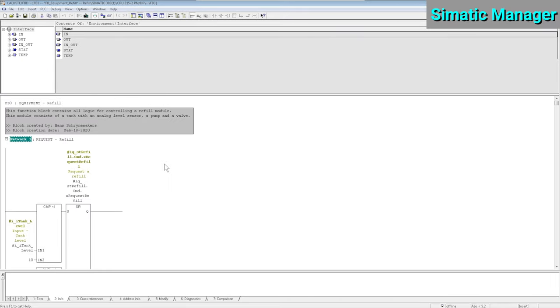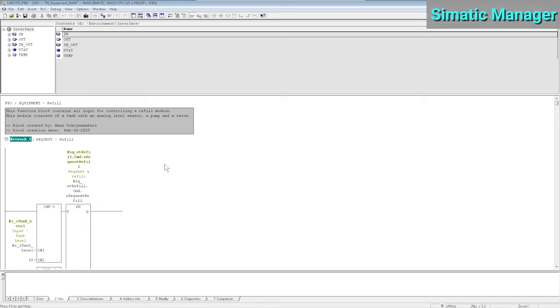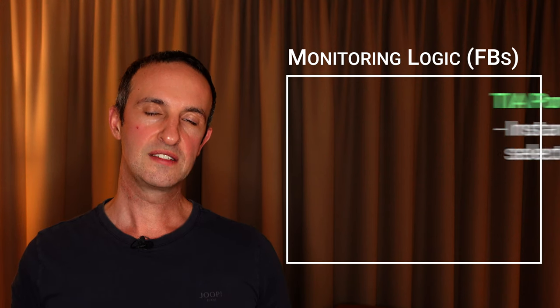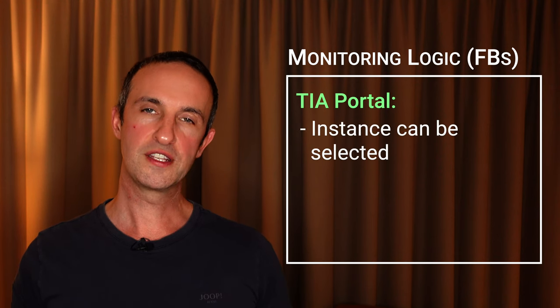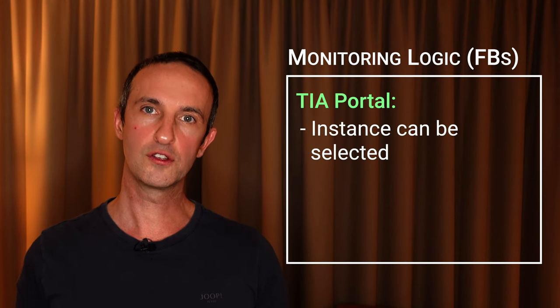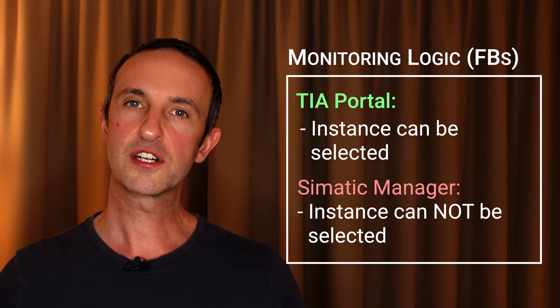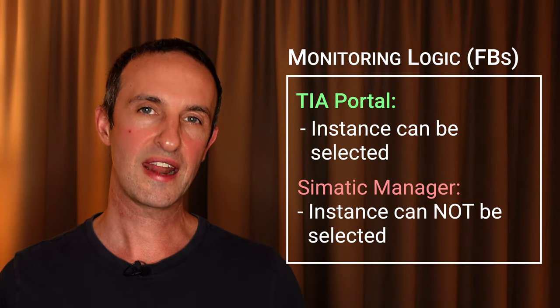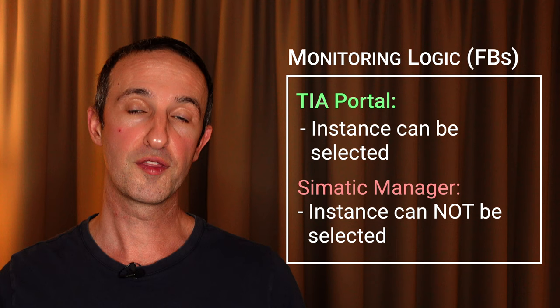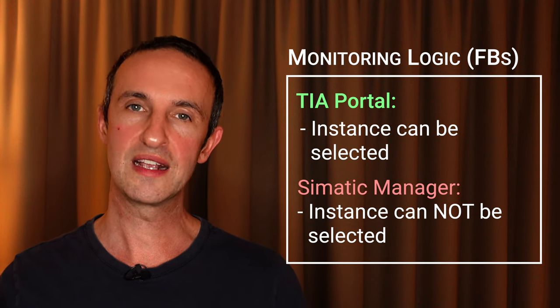In Simatic Manager you do not have the option to select your call environment. If you would like to monitor a specific instance of a function block that's being called multiple times, then you need to first disable the calls for the other instances. Adding an always off tag in front of the call does the trick. Here again lies the real probability that you forget to enable those instances again after you're finished with troubleshooting, leading to an application that does not work anymore. The bottom line, when it comes to monitoring logic inside your function block, TIA Portal offers you the option to select which instance you would like to monitor. Simatic Manager simply does not have this option.